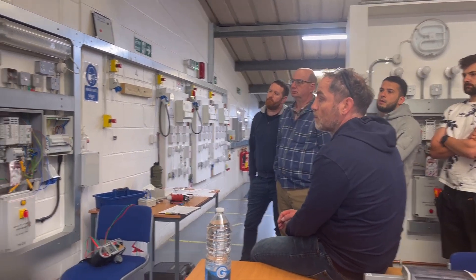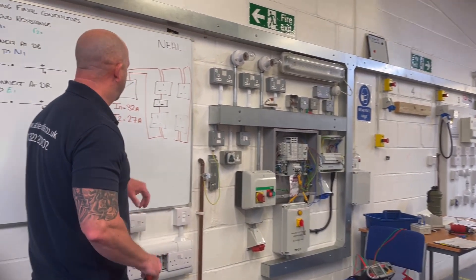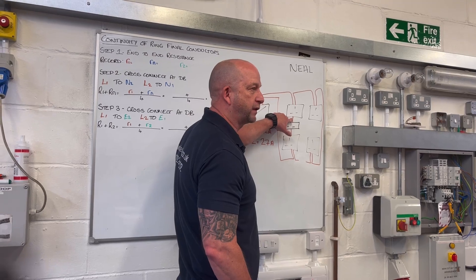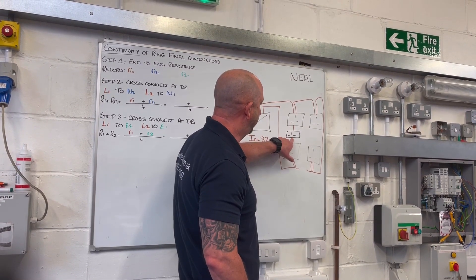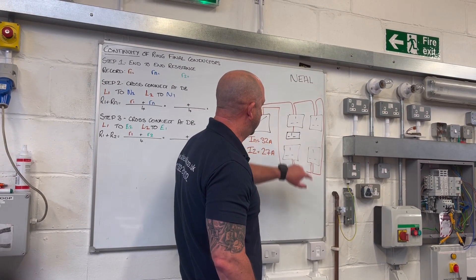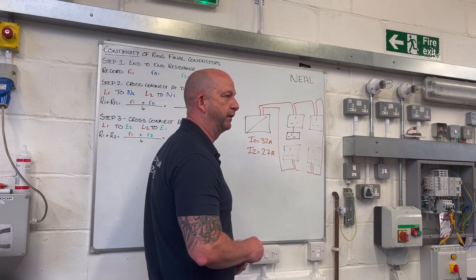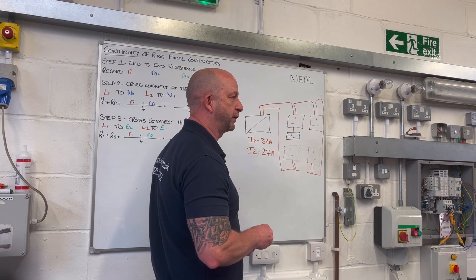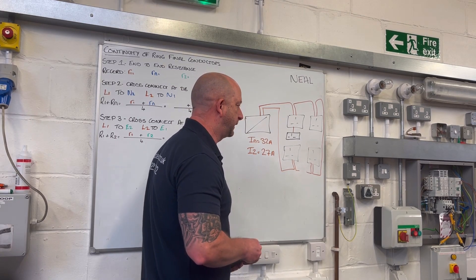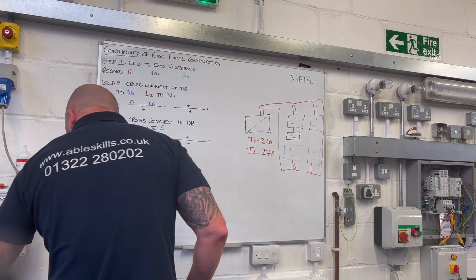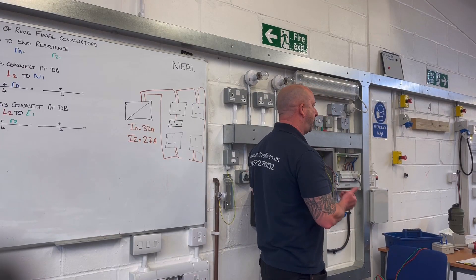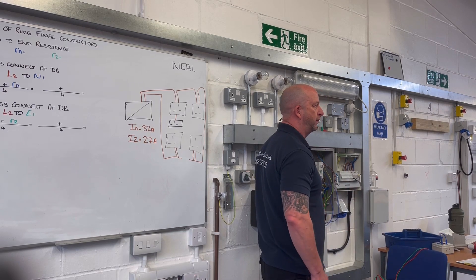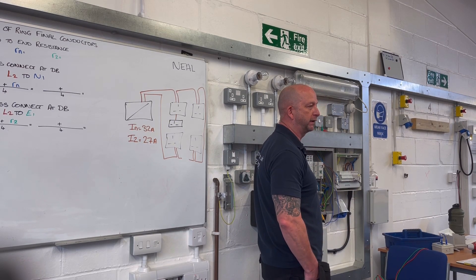So our ring final test, guys — there are three things, really. It's going to make sure that all our sockets are connected in a ring final. It will identify anything wired as a spur, and also it'll identify any hideous interconnections or figure-of-eight wiring. And also, as you said, steps two and three combined will also prove polarity. So that's why we're doing it differently than we would on any other circuit.